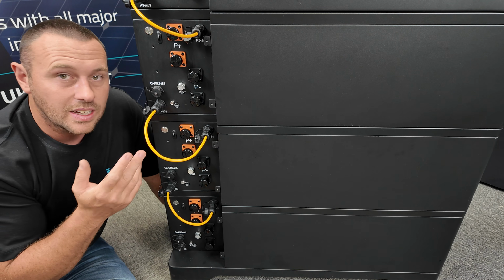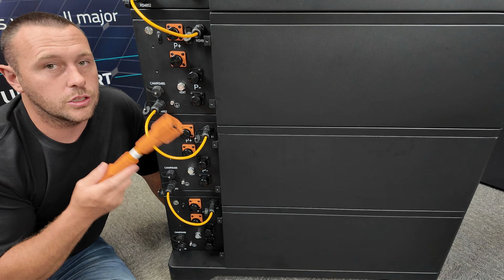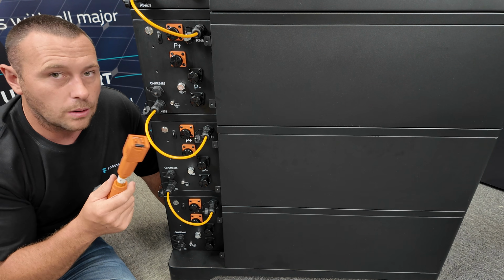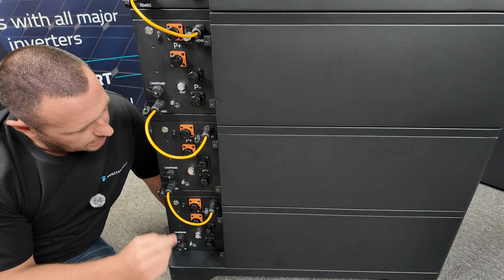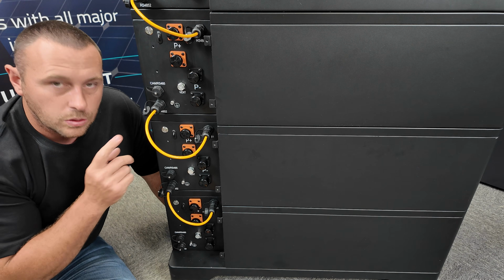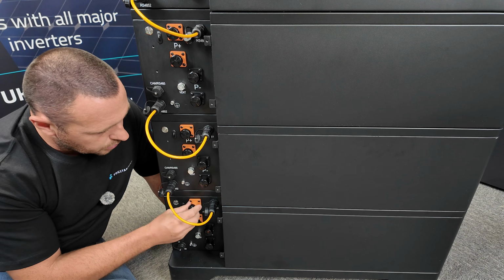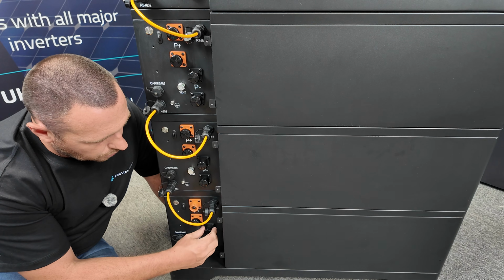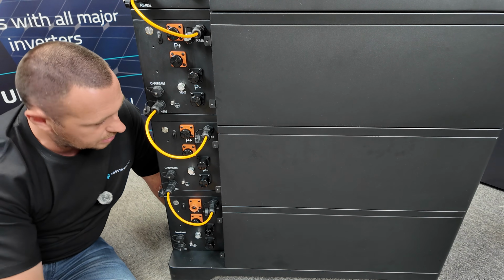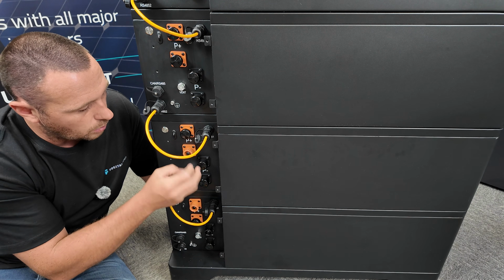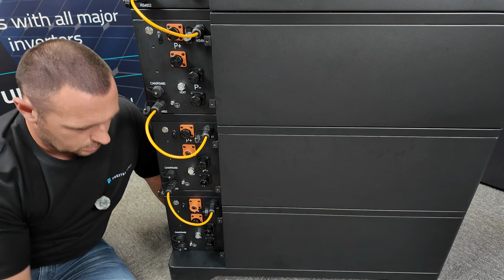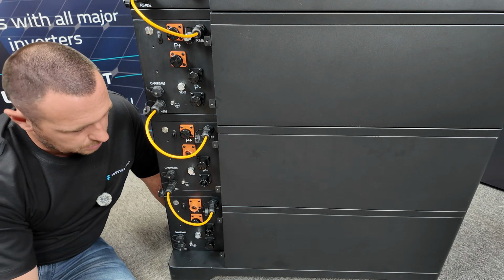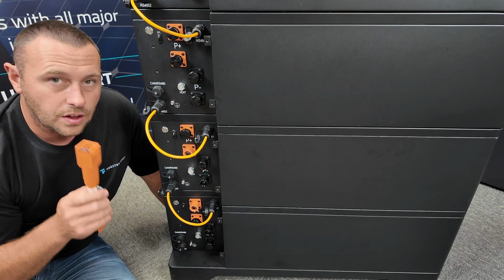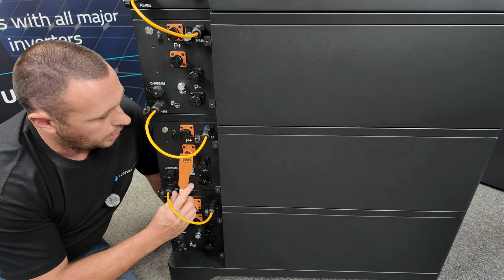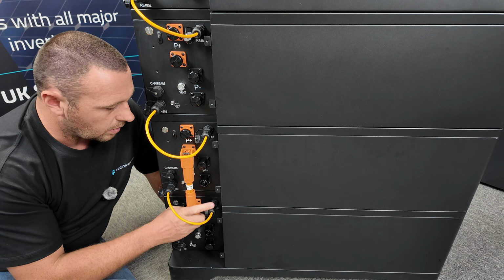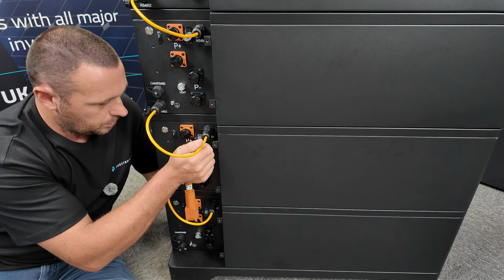Now that the comms cables are in and done, we're going to turn our attention to the battery parallel power cables. So these are going to go from module to module. So on the lowest battery module, we want to remove the upper of the positive and negative dust caps, and the lower of the module above, positive and negative dust caps. These are quite stiff and they are quite tricky to fit, but they do go in. They are the right size. You've just got to give them a bit of a wiggle.